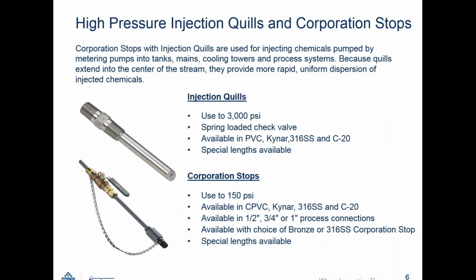High pressure injection quills and corporation stops. When injecting chemicals into a water line, it is recommended to have a quill or an injector to properly disperse the chemical into the line. And these 2 items here, the injection quill, which is a fixed piece that goes into a line, can inject the chemical into the pipe.